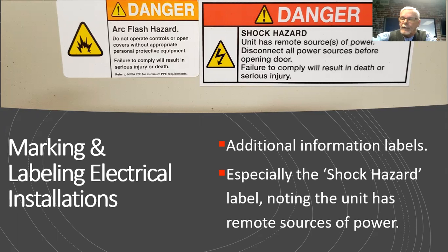Those are more specific. They tell you what the incident energy is at any given point in your process. If you do that, then you have that on the label: this is the incident level, these are how many calories per centimeter squared we're going to be involved with, what is my prohibitive boundary, and what are the individual PPE requirements?